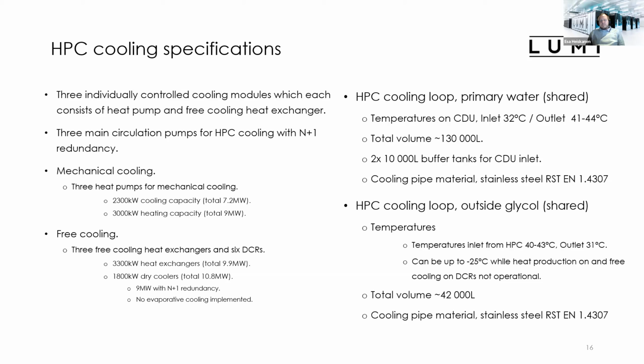This outside cooling loop can go down to minus 25 degrees Celsius while heat production is on in the winter time, and free cooling on the dry coolers is not operational. I will tell later what kind of issues can happen with the cooling, but it can get quite cold. That's the reason we need to use glycol outside. We cannot use water. The total volume of this is 42,000 liters, and it's also made from stainless steel.